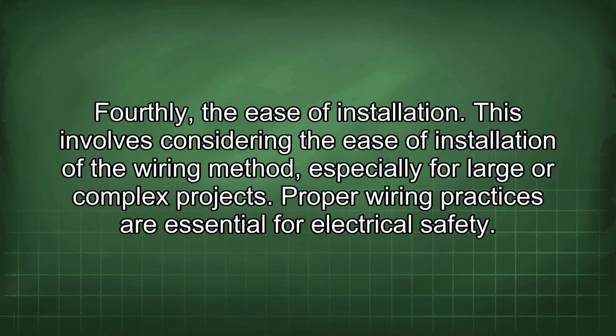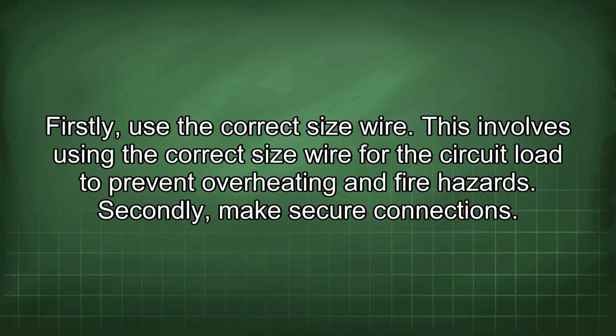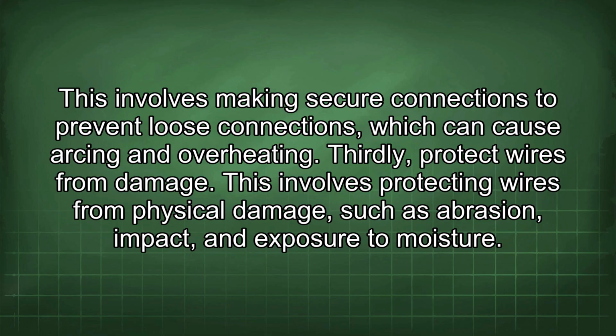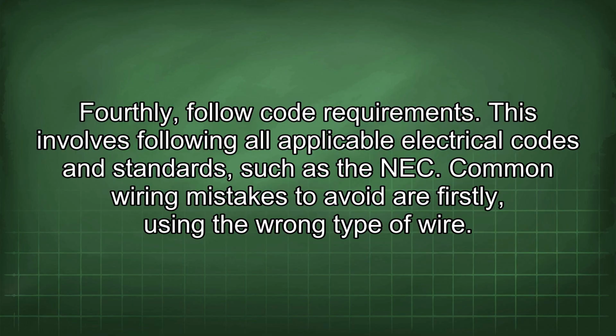Proper wiring practices are essential for electrical safety. Firstly, use the correct size wire. This involves using the correct size wire for the circuit load to prevent overheating and fire hazards. Secondly, make secure connections. This involves making secure connections to prevent loose connections, which can cause arcing and overheating. Thirdly, protect wires from damage. This involves protecting wires from physical damage, such as abrasion, impact, and exposure to moisture. Fourthly, follow code requirements. This involves following all applicable electrical codes and standards, such as the NEC.